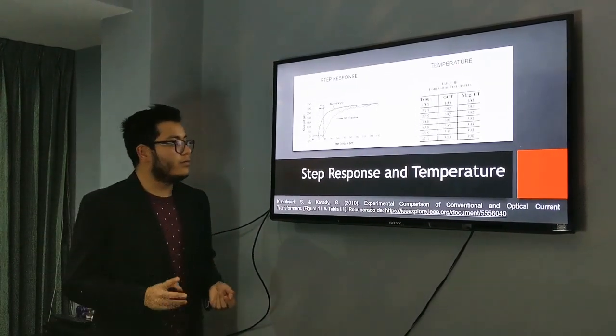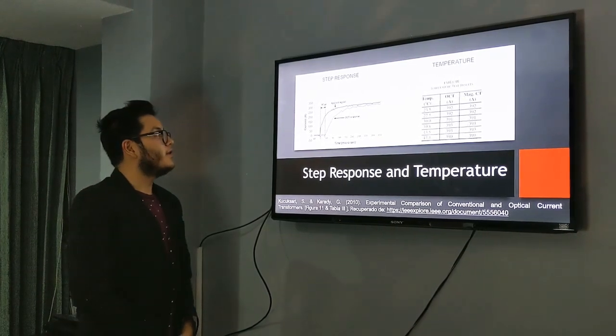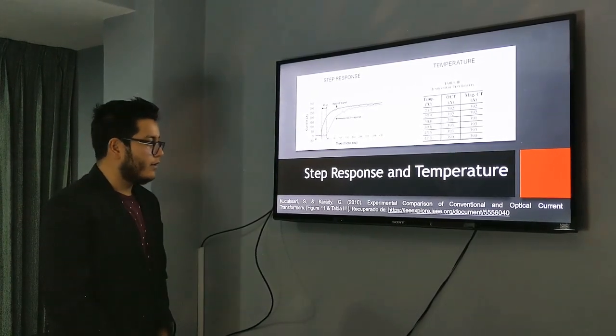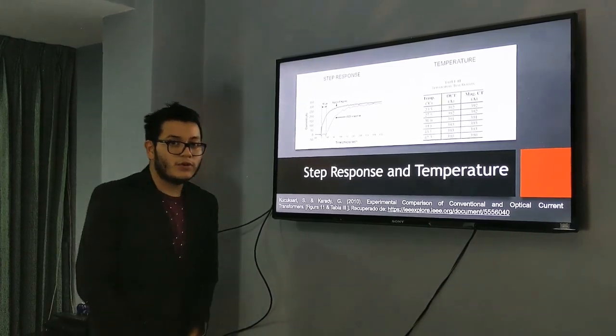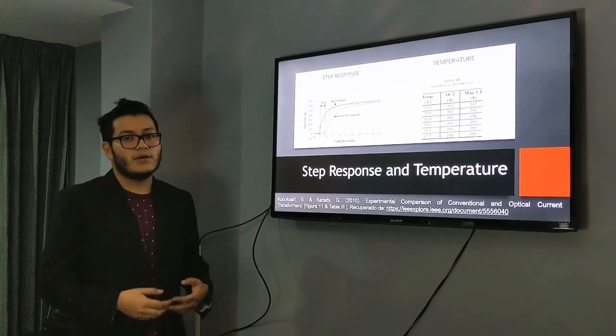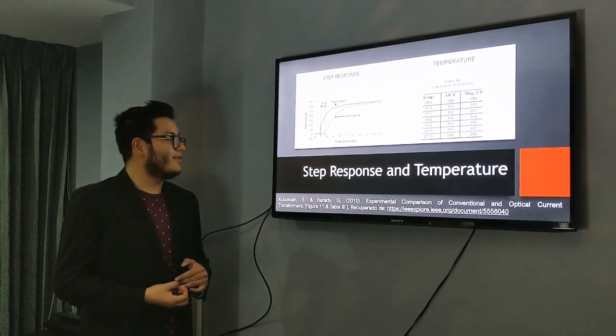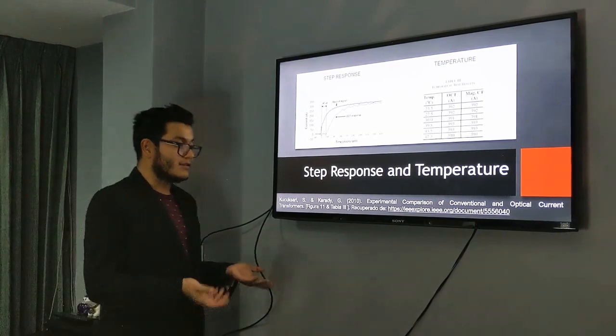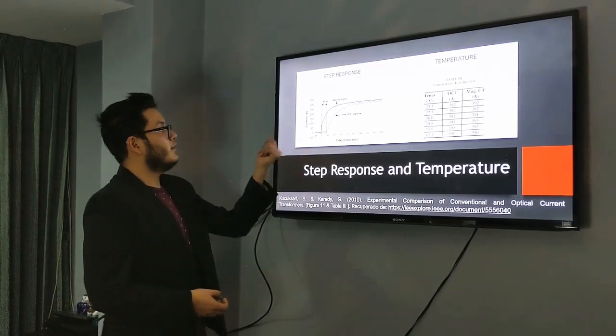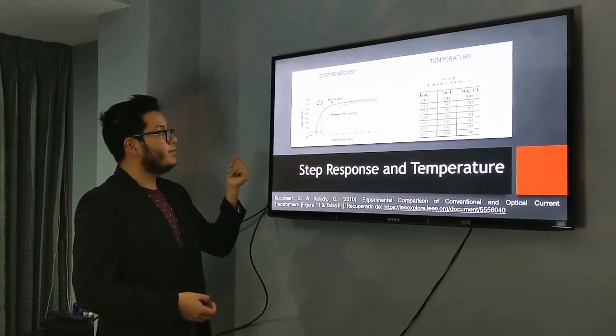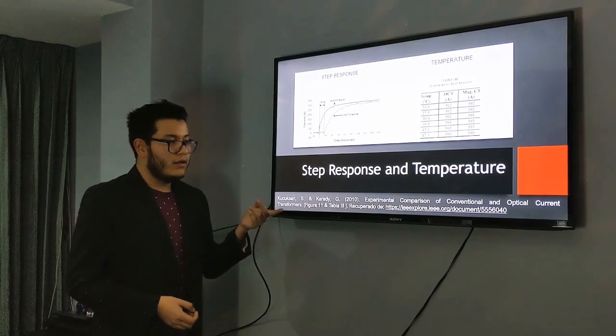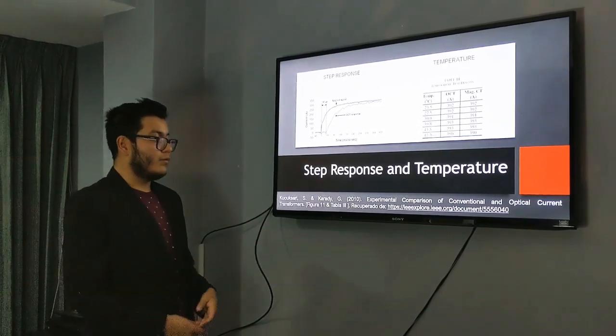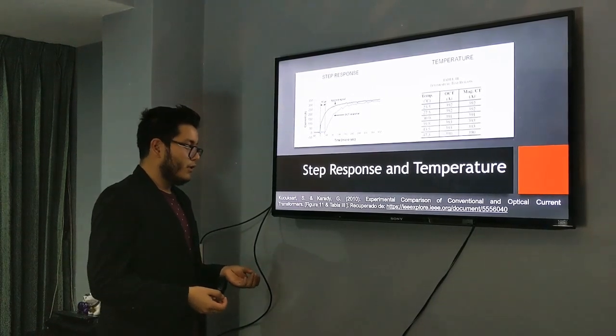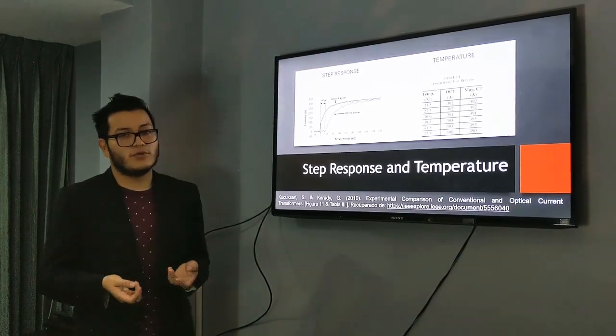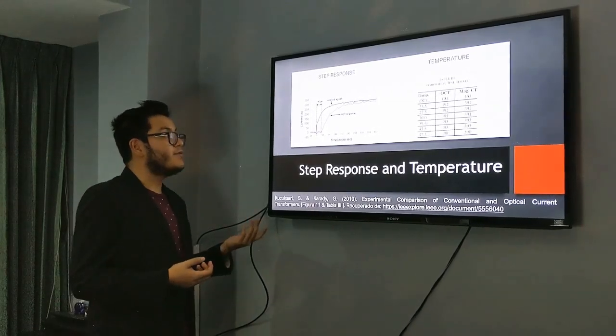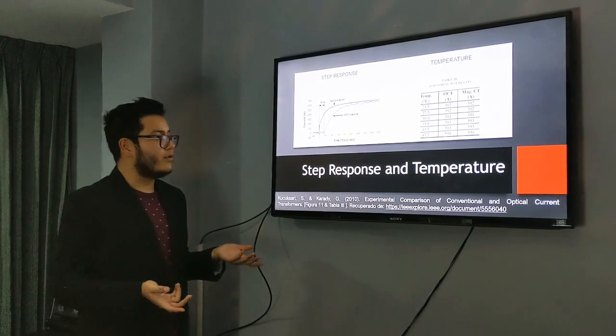And the last two tests were made especially just for an optical current transformer. The first one being the step response, so we can see how our optical current transformer behaves against a step response. In this case, here is the graph, and you can see that the step response has a 40 microseconds delay. But we can see that it's not much of a difference. It's really a small time of difference between the step response and the response the optical current transformer has.